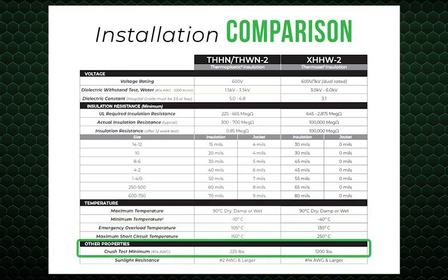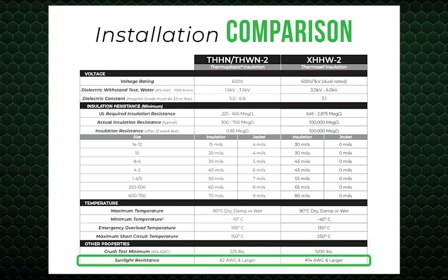A cable's crush test minimum will provide insight into its ability to handle stress during installation. Higher crush test resistance means a more durable cable. Service wire's XHHW-2 thermoset XLPE compound has almost 5 times the crush resistance as THHN. Sunlight resistance is an important consideration for outdoor installations. Over time, sunlight will drive the plasticizers out of the thermoplastic compounds, making them fade and become brittle. Thermoset compounds have superior sunlight resistance, allowing for longer service life. Service wire's XHHW is listed as sunlight resistant from sizes 14 gauge to 750 kcmil.